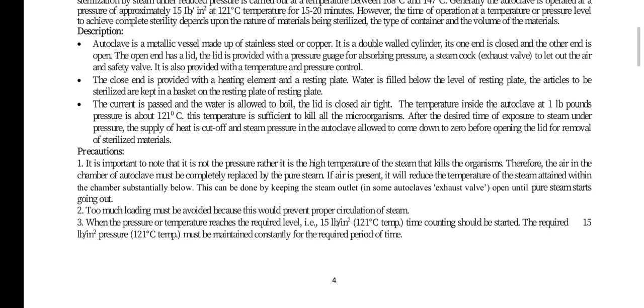The closed end is provided with a heating element and a resting plate. Water is filled below the level of the resting plate. The articles to be sterilized are kept in a basket on the resting plate. The current is passed and the water is allowed to boil. The lid is closed airtight.